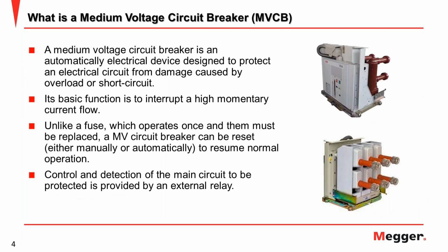Okay, now go to the explanation about the MV circuit breaker. Actually, the definition of a circuit breaker based on IEC will be the same for the MV or LV. So a medium voltage circuit breaker is an automatically operated electrical device designed to protect an electrical circuit from damage caused by overload or short circuit.